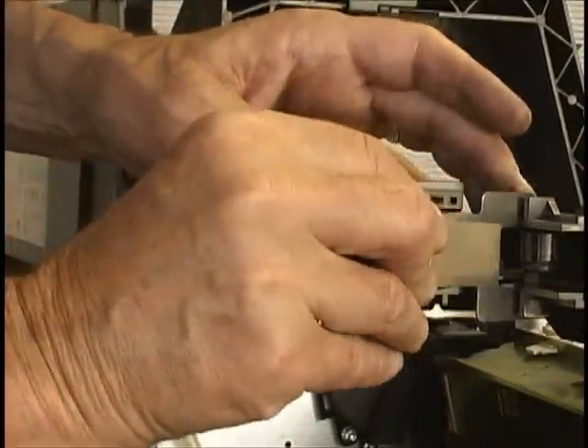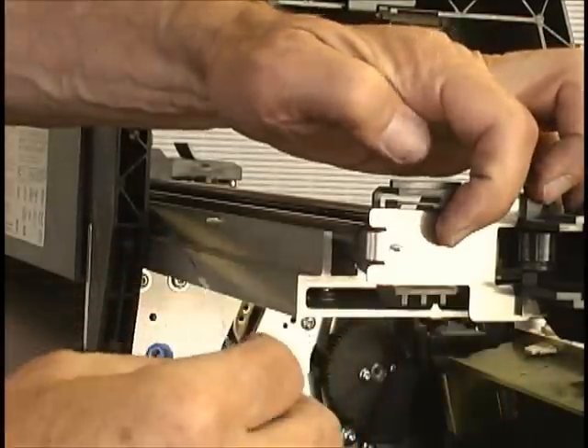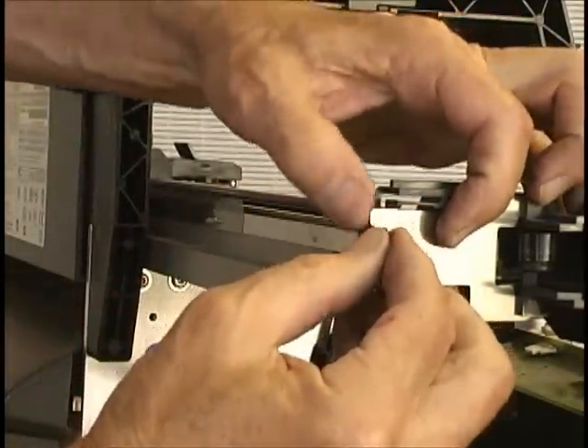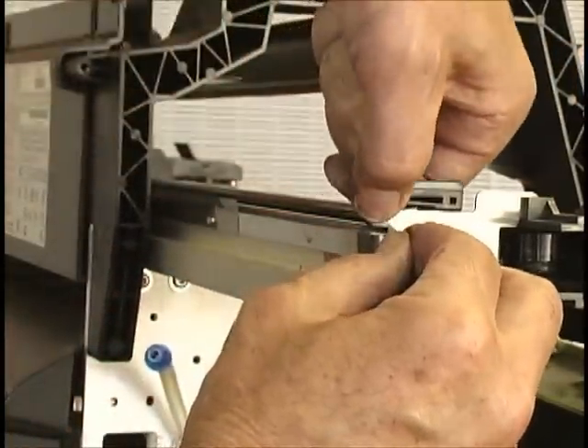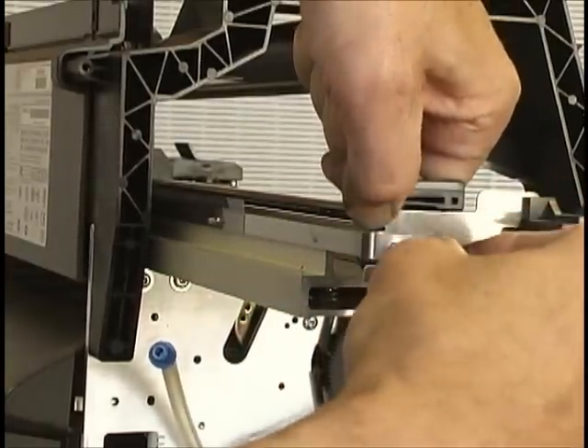I'm going to put the encoder strip back together, so I'll need to put the spring steel back here. This is the encoder strip, the end. I'm going to have to bend that in quite a bit and slip it over there, and that will stay put until we get this nut on.